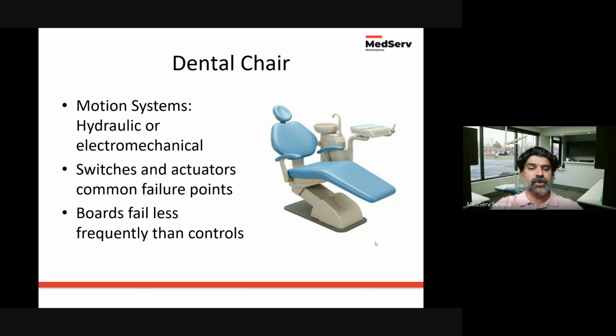This motion is typically controlled by means of hydraulic or some sort of electromechanical system. And so there are a lot of switches and actuators involved in this process that have typical failure points in them. Usually the chair is also utilized as the way to distribute the air, water, vacuum, and electrical to a lot of the attached devices too. Most of the time, it's more of a component than a PCB board or a motor controller that's failing on the chair itself. So it ends up being a lot easier to fix and repair than it may initially appear to be.